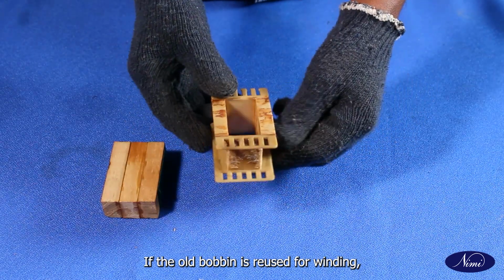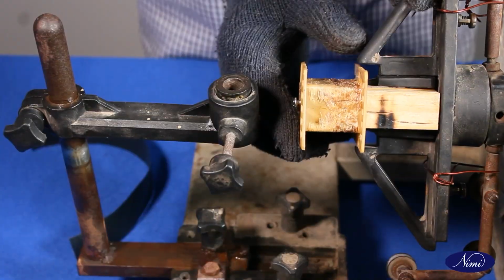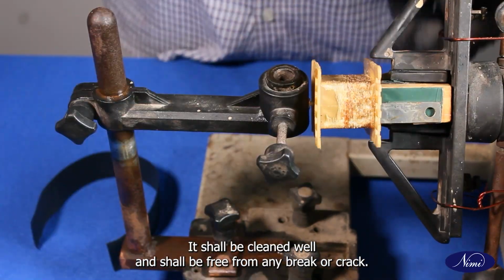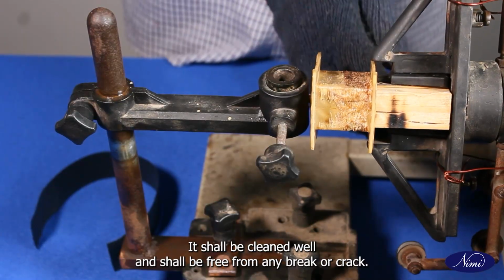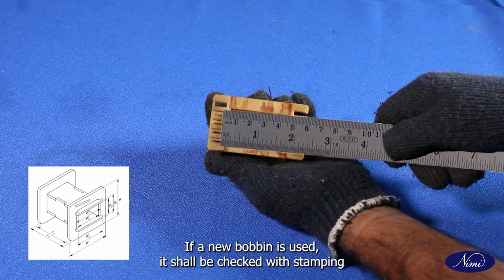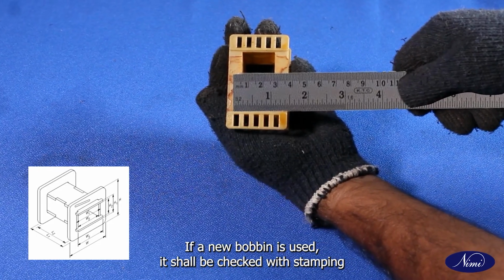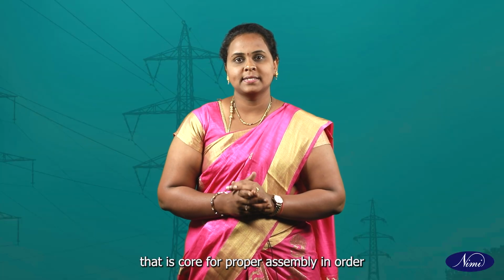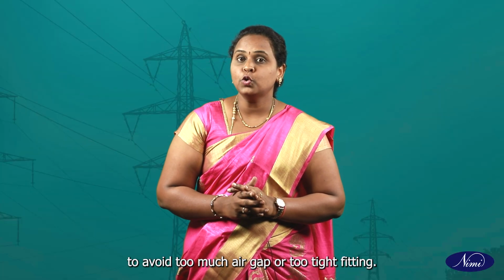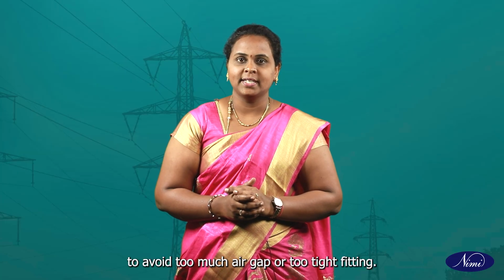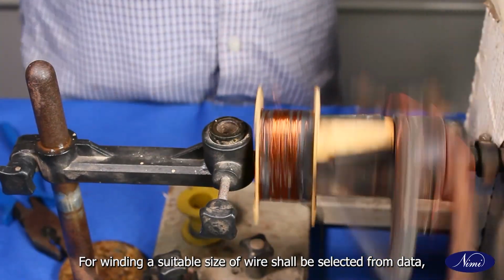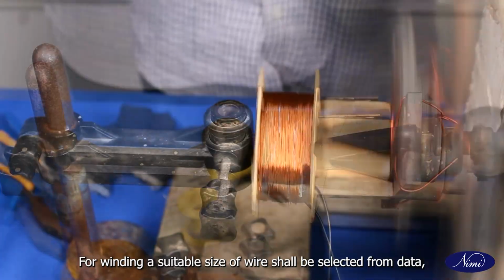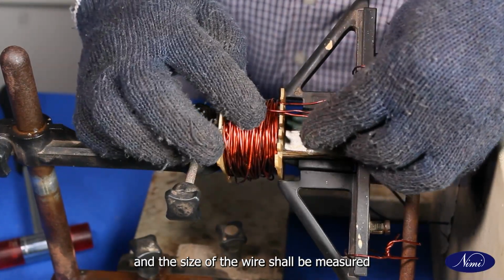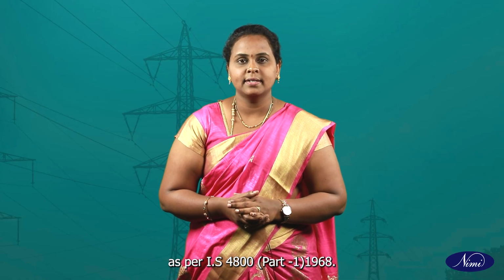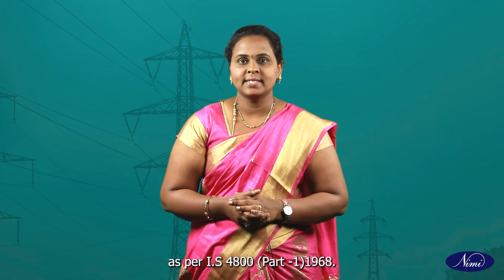If the old bobbin is reused for winding, it shall be cleaned well and shall be free from any break or crack. If a new bobbin is used, it shall be checked with stamping, that is core, for proper assembly in order to avoid too much air gap or too tight fitting. For winding, a suitable size of wire shall be selected from data and the size of the wire shall be measured as per IS 4800 Part 1 1968.